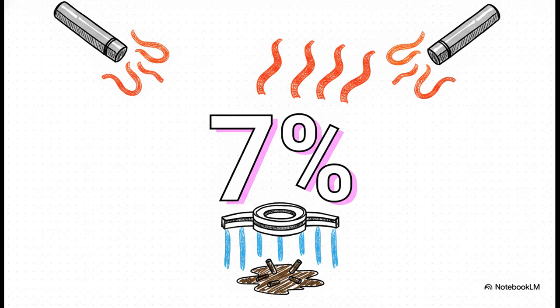The very moment a reactor shuts down, decay heat immediately accounts for about 7% of the pre-shutdown power level. Now, 7% might not sound like a ton, but if you have a reactor that was operating at 3,000 megawatts thermal, the exact second you hit that shutdown button, it is still generating 210 megawatts of pure heat. That is definitely not negligible. It is more than enough to completely melt the nuclear fuel if active cooling is somehow interrupted.